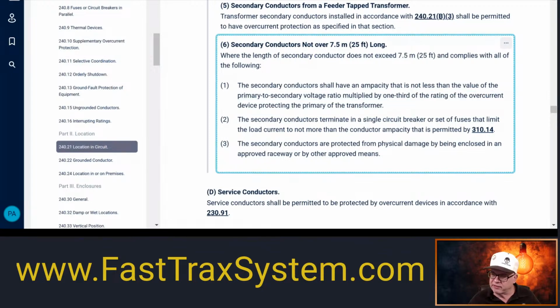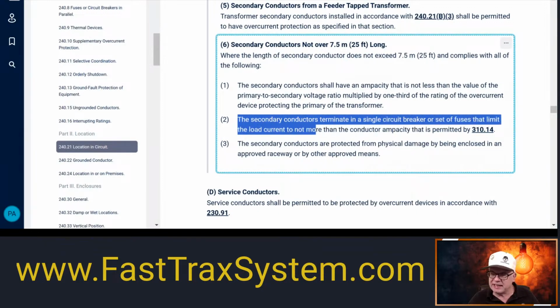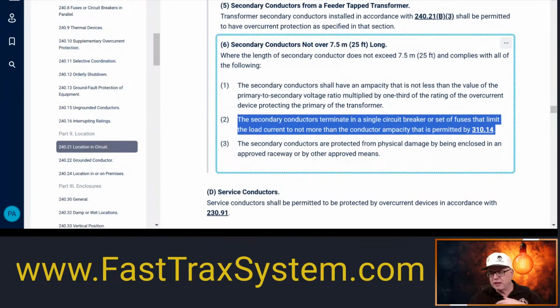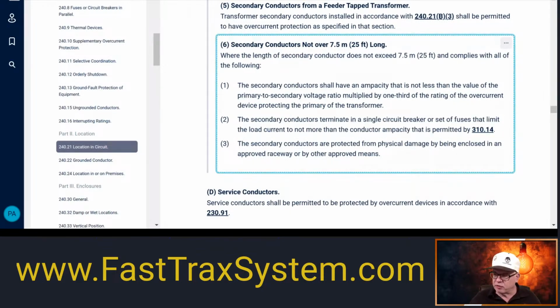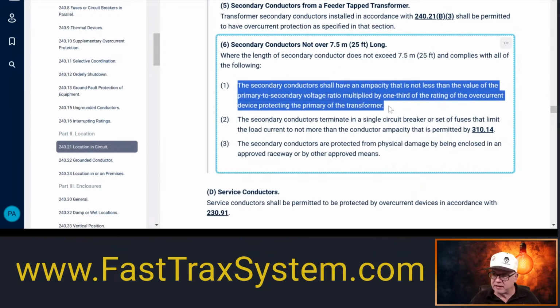Well, next thing we look at, it says that secondary conductor has to terminate in a single circuit breaker or set of fuses that limit the load current to not more than the conductor ampacity that is permitted in 310.14, because we have adjustments, corrections, other things that can take place in 310.14, which ultimately sends you to things like 310.15 B2, B1 or C1, things like that. And you could have ambient temperatures. It means that conductor's ampacity may have to be adjusted or corrected in some way, right? So basically it's telling you that it has to terminate into a circuit breaker, or it could be a fuse set, okay? And that fuse set has to limit the current to not more than the conductor's ampacity. Well, we already know what the minimum of the conductor's ampacity is.